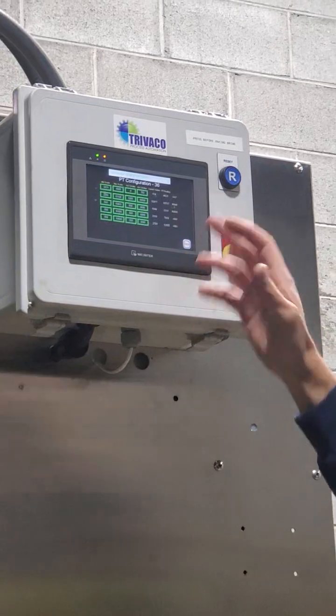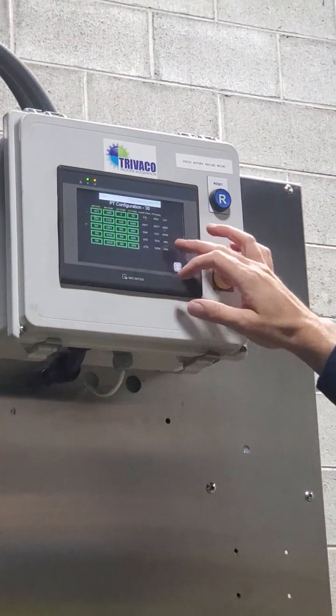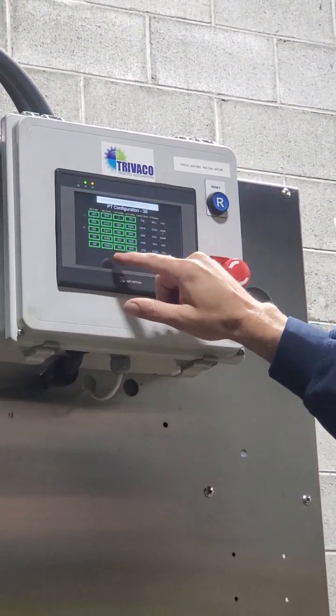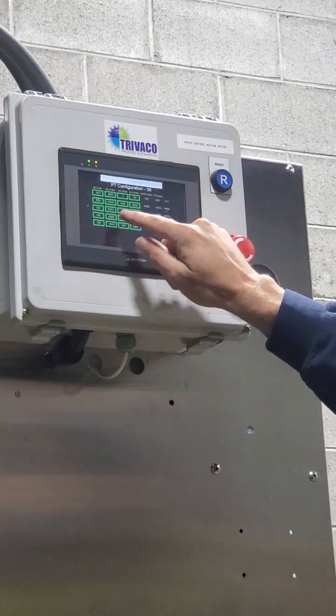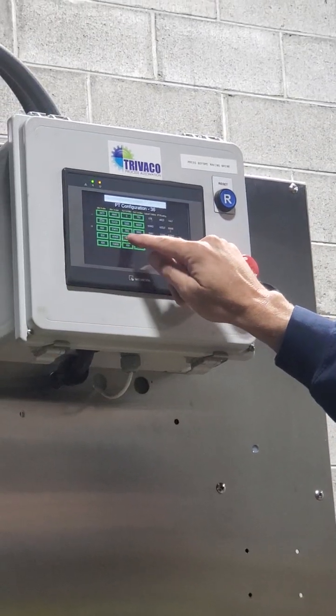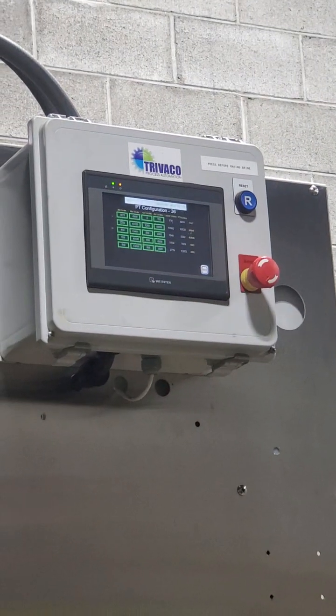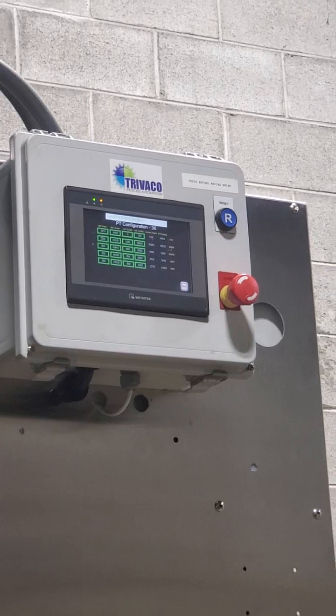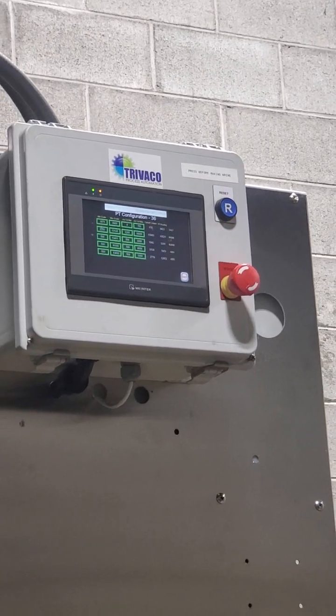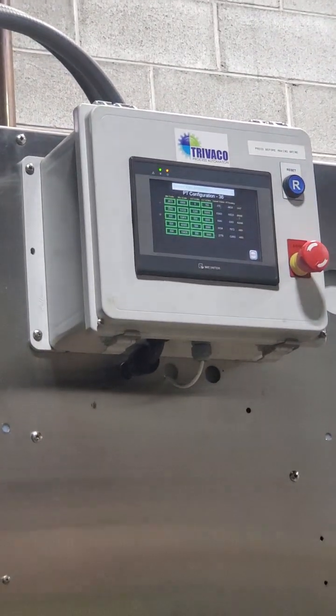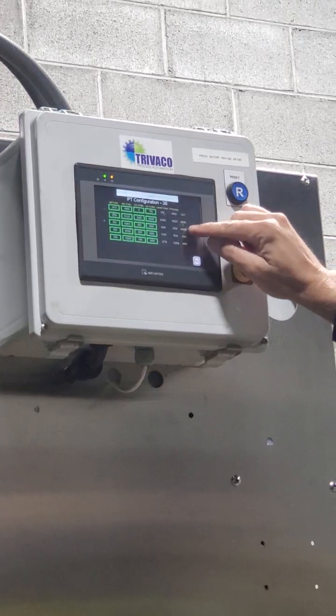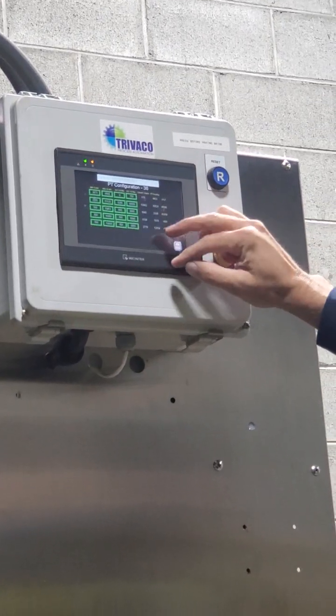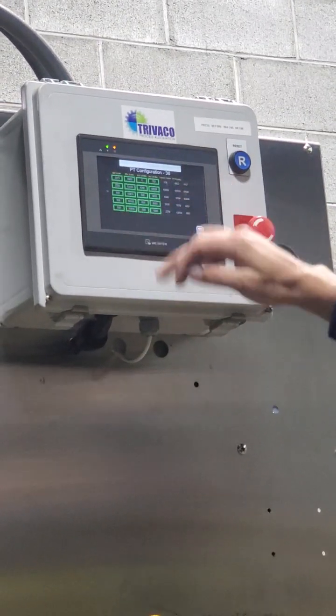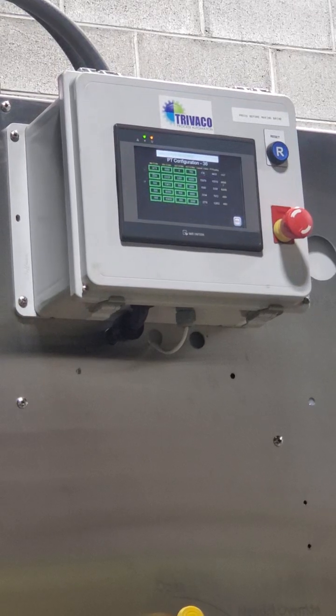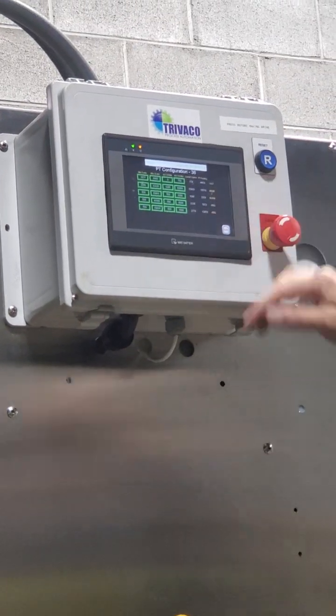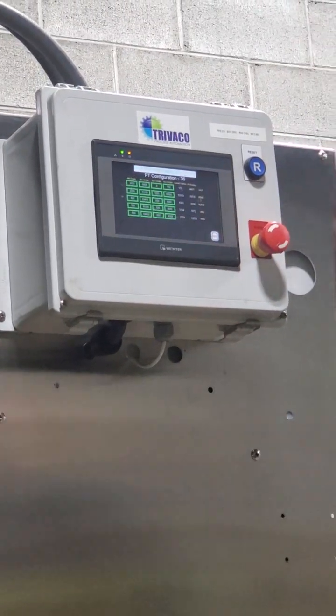When you're out there filling trucks, it's going to stop when it hits that PT number that represents 500 gallons. It won't let you draw out too much liquid, because you don't want to run it dry. On these, that's the number we're more worried about, the lower set point on these settings, rather than the capacity itself. For brine, you're worried more about capacity, so you don't overfill it.